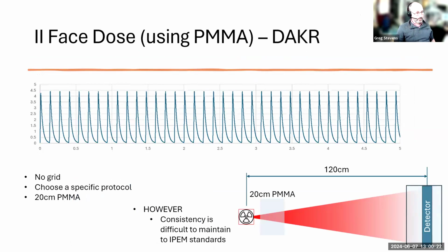The other thing that's quite interesting is just how fast the system reacts. I did a lot of messing around with taking everything out of the beam and then putting 20 or 30 centimeters of PMMA in the beam, and it reacts within a pulse. Our pulses are 7.5 frames a second, so within a pulse is pretty quick for most electronics.